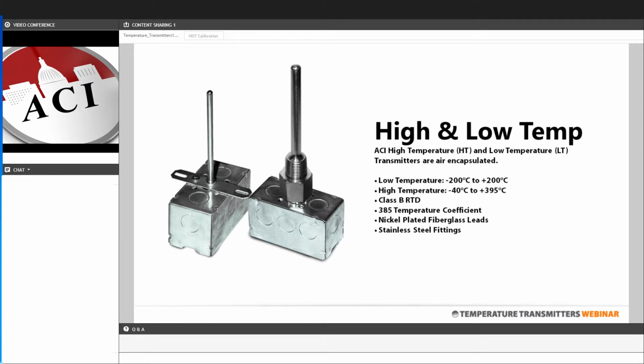As mentioned a few minutes ago, because temp transmitters provide a linear and stable output, we have the ability to do these in very high temp and low temp units, as low as minus 200 degrees C for our low temps and as high as 395 above 0 C for our high temps. These use Class B RTDs and all stainless steel fittings and components to meet the tolerances of those very high and low temperatures.